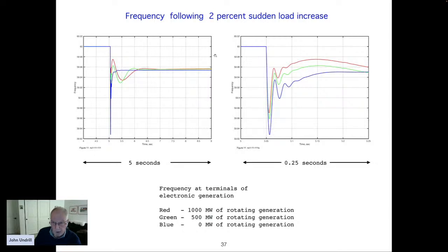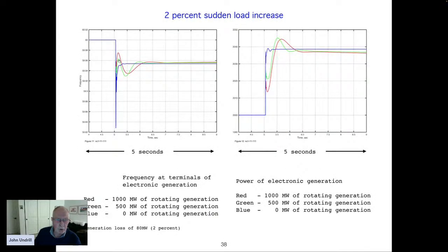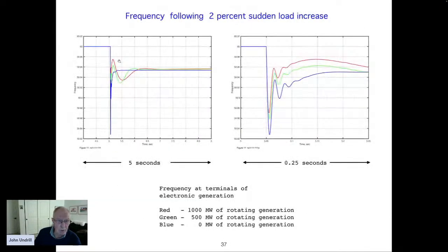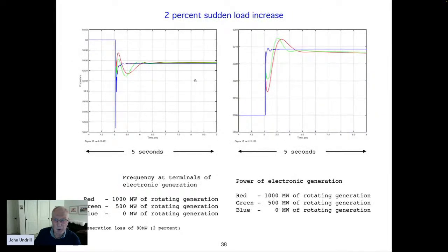Let's go to the next slide. This is the same 5 second plot of frequency from the previous slide. Here's what the power of the electronic generation would have to do in order to stabilize the system like this. So this is a 5 second span. Frequency settled out more or less within a quarter second and settles to a steady value. Not at the original value, but according to the droop equation. And then it's ready for secondary control to bring it back up.